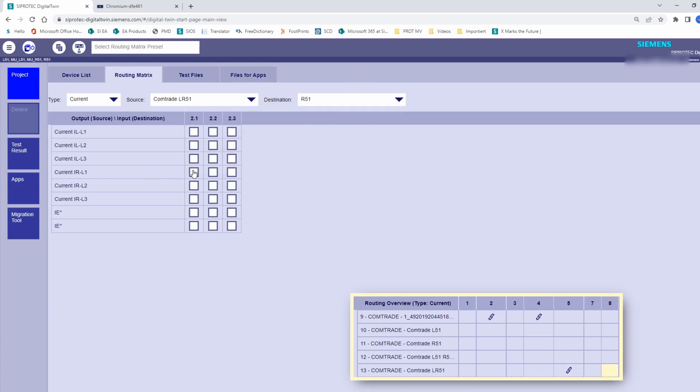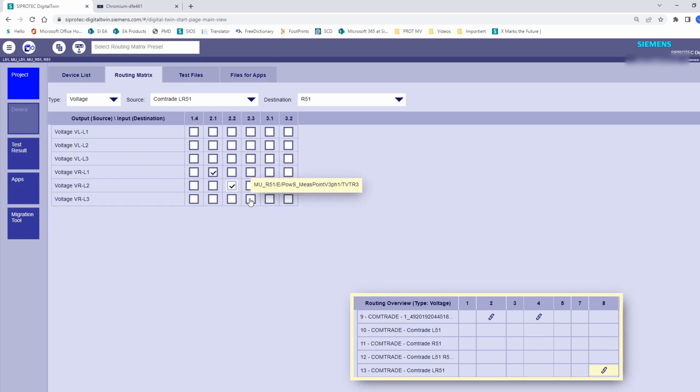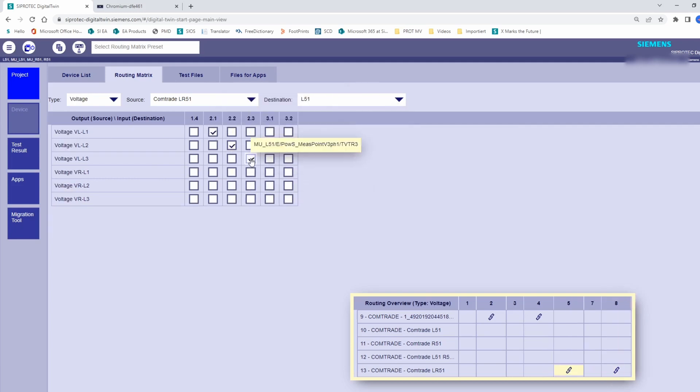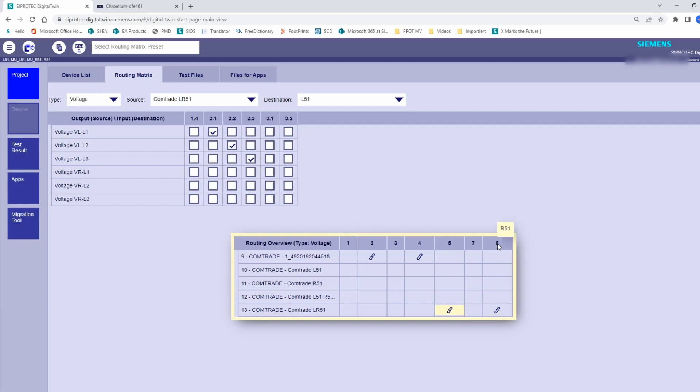After that, we do the same for the device located at the right end of the line. So, we connect here also phase 1, phase 2, and phase 3. We do the same with the voltages. There is a summary table here where you get the routing overview. This view shows for example, that the voltages of the COMTRADE LR51 have been assigned to device 5, and if you move your mouse closer, you will see the name of the device, in this case L51. Voltages have been also connected to device 8, which is the R51. Keep in mind that the routing shall be done when the simulation is stopped.